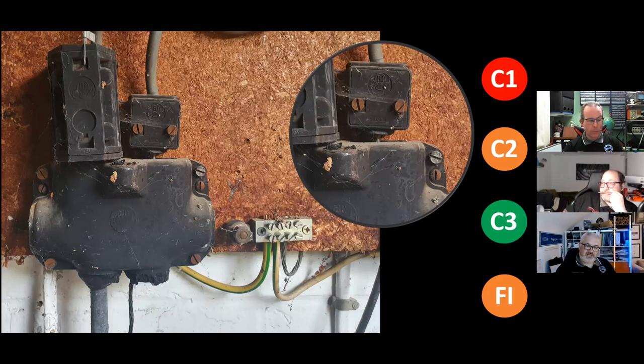I can see a lot of people say it's a C2, because again, it depends on your assessment of risk of accessibility. Could you maybe put some sort of shielding around that? Is that a matter of opening up them screws, undoing the neutral terminal and lowering it down, which we're not authorized to do, which is one of the nuisance things. Again, I think DNO training should be in electricians' training.